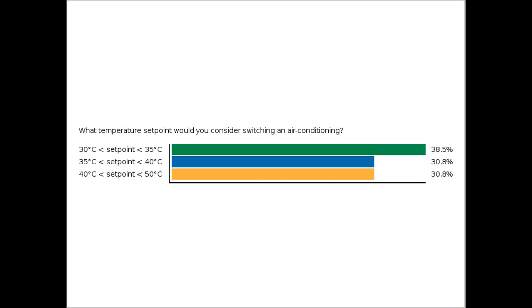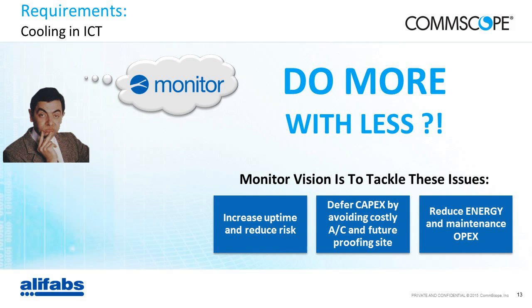So we have to think really strategically, and our initial thought was to do more with less, keep things as simple as possible, with the main objective being to increase the uptime and reduce risk. If I compare a free cooling system with an air conditioning system in the middle of the summer and you hit a high temperature alarm, the one which will need site intervention would be the air conditioning, because the free cooling system is very likely to clear its own alarm, especially over the night time. So that's how we increase uptime and reduce risk.